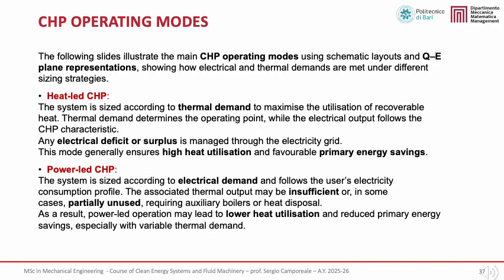Now, we compare heat-led and power-led CHP systems and highlight their main operational implications. When a CHP system is sized according to thermal demand, the configuration is known as heat-led CHP. In this case, the cogeneration unit is designed to maximize the utilization of recoverable heat, ensuring that the user's thermal demand is fully met. Any additional electrical energy required is supplied by the electricity grid, while excess electrical production may be exported, exchanged, or sold.